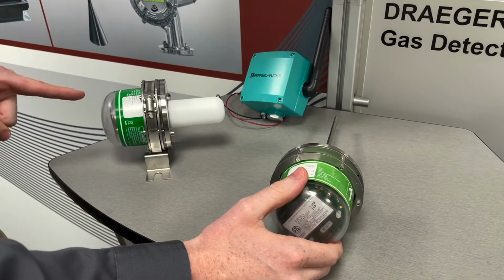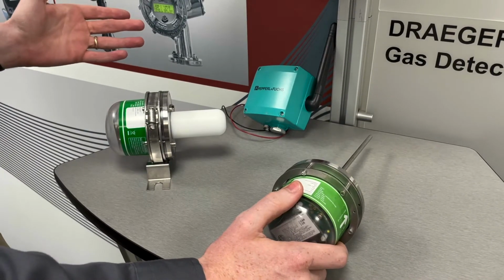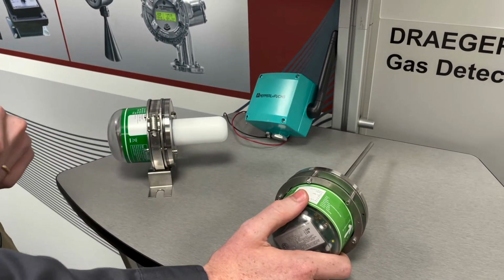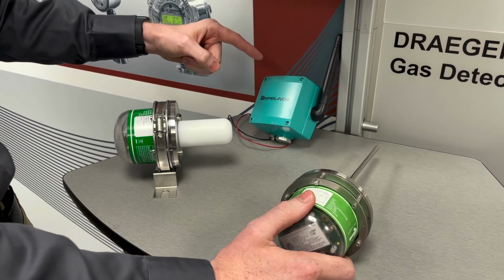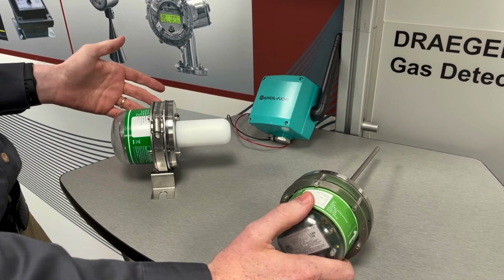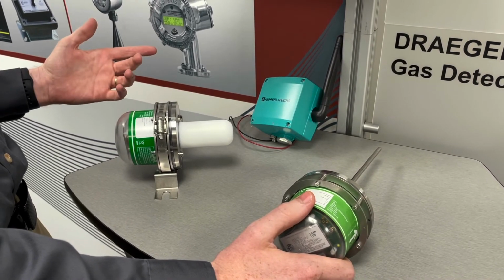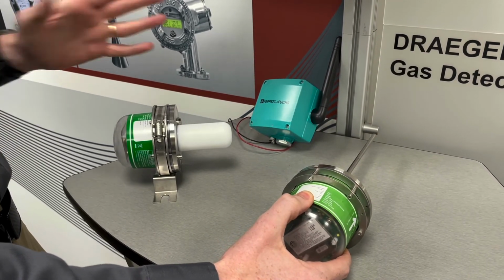There's 3 elements to an instrument area network: the gateway, the collector, and the transmitter. The reason we split it up into these 3 elements is because the collector and the transmitter communicate over Bluetooth Low Energy. The collector and the gateway communicate over the wireless HART protocol. Now, this is done in order to maximize battery life. And this is what sets apart Instrument Area Network: a 10-year guaranteed battery life for end-node transmitters. This battery life is unmatched by any of our competitors.